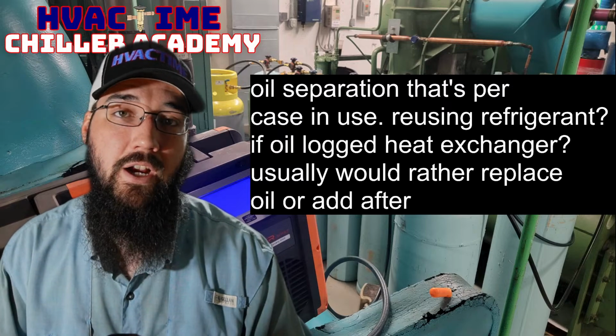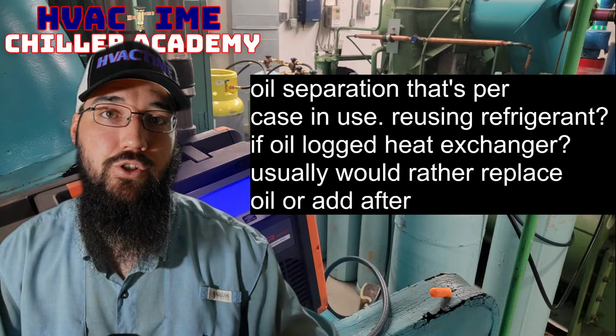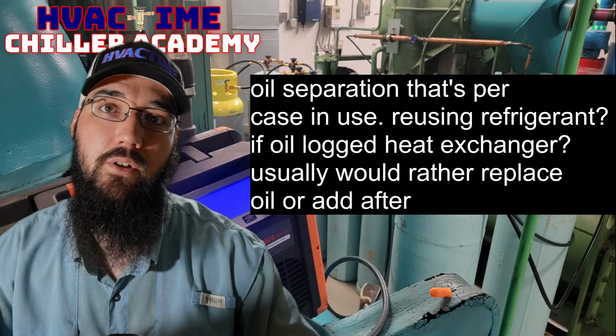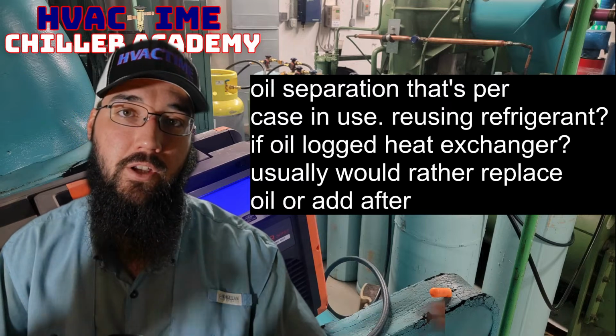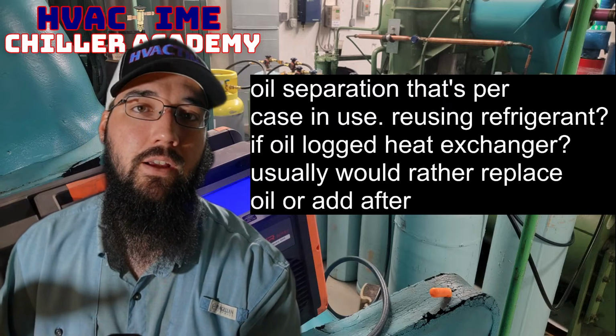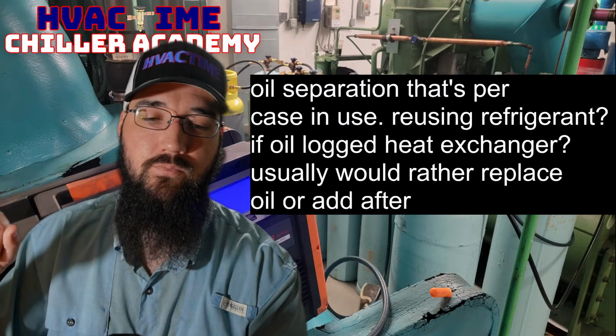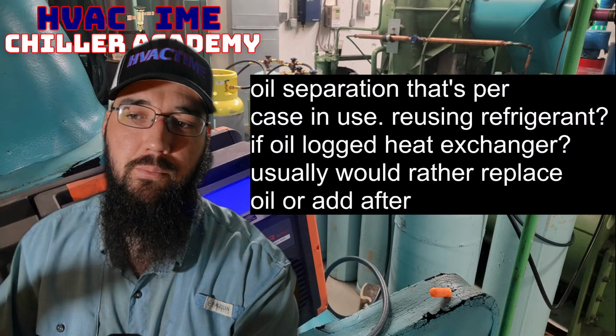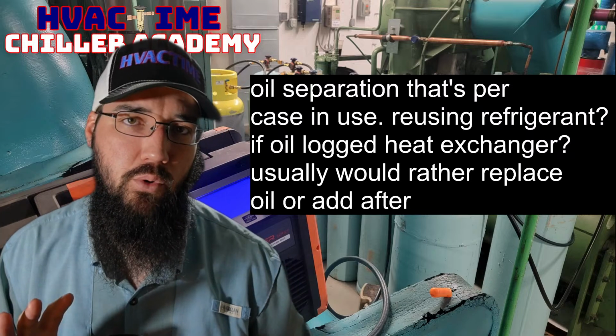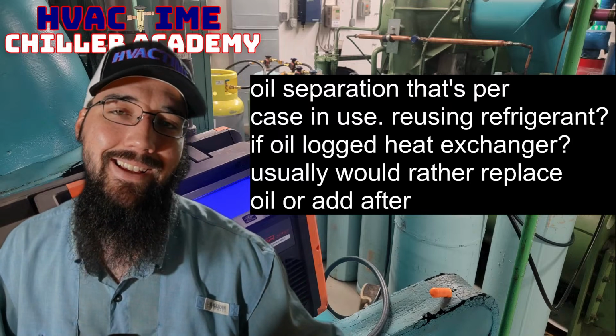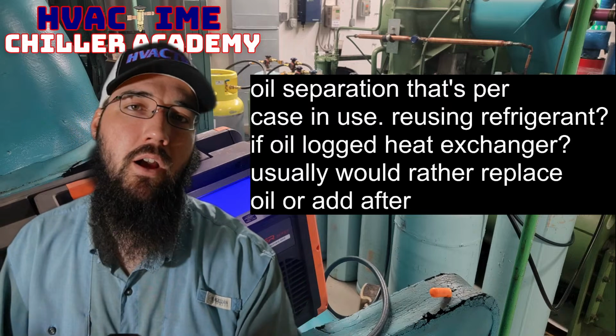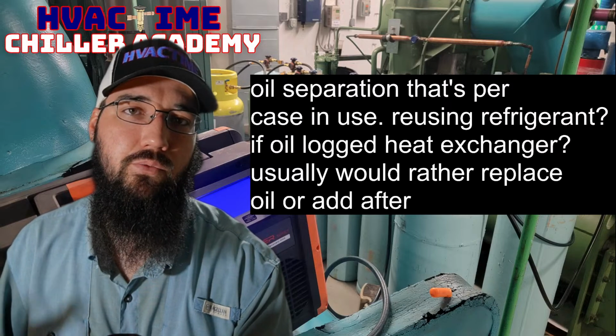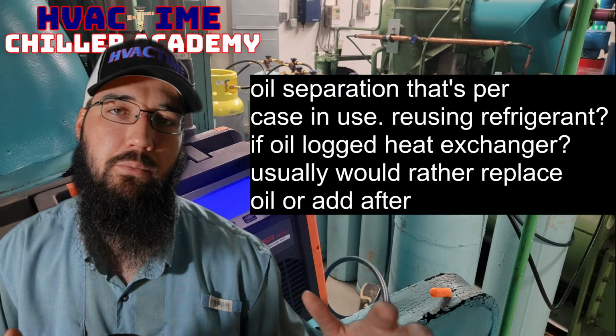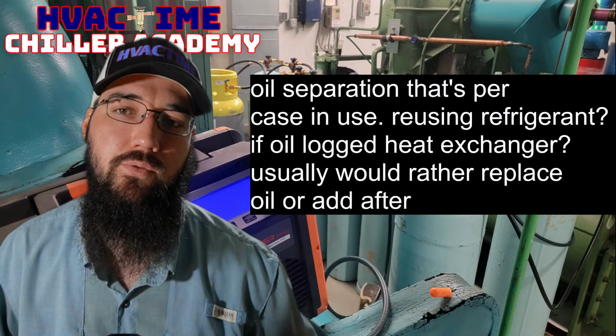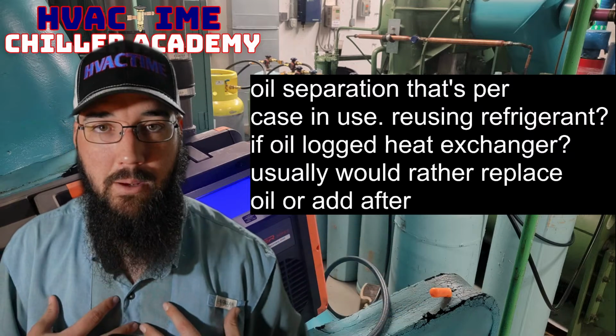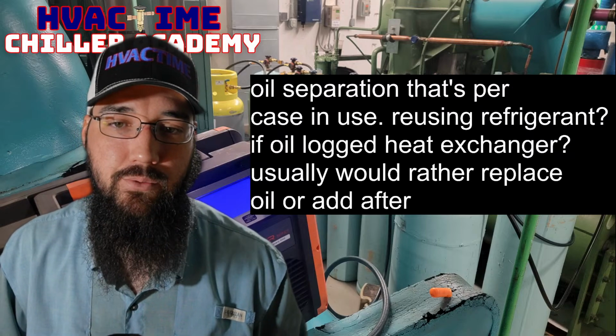Recover the system down, try my best to judge getting the worst of the oil-laden refrigerant, which is going to be on top, into a specific cylinder. From there, I can try to boil that refrigerant back out of that oil and get the refrigerant back, but I'm not going to try to re-put that oil back into the system. I'd much rather just add fresh oil for whatever was lost. That's my personal preference in that situation.